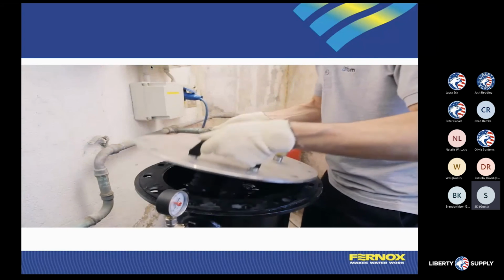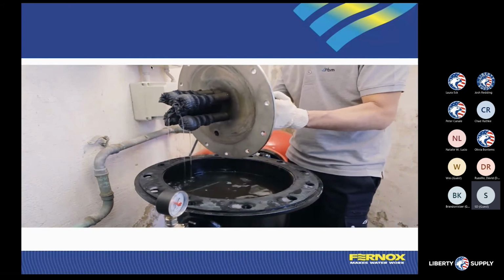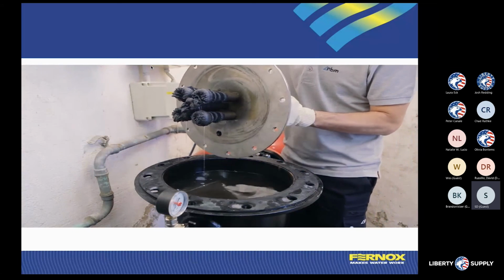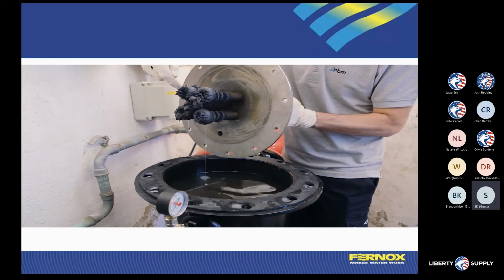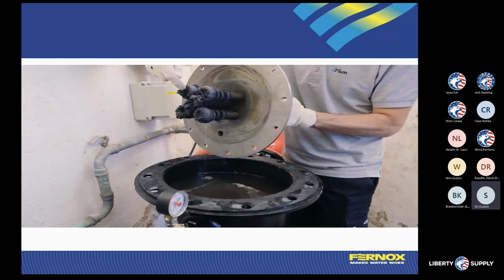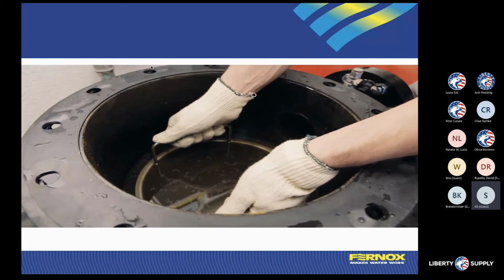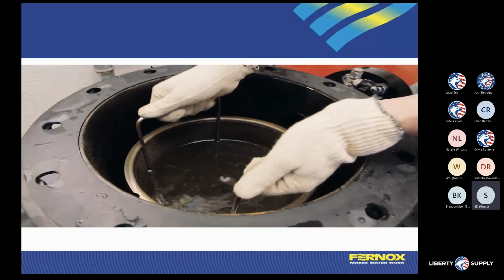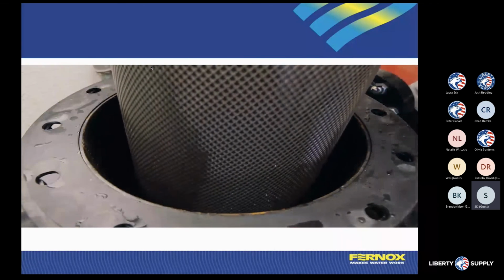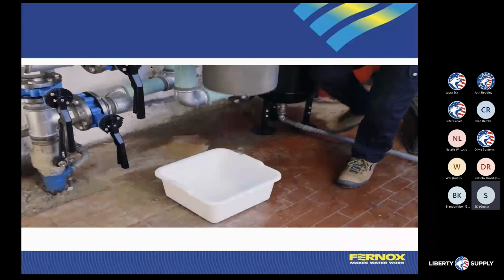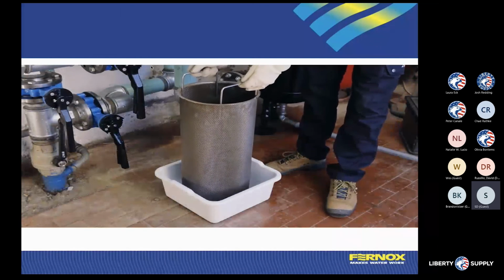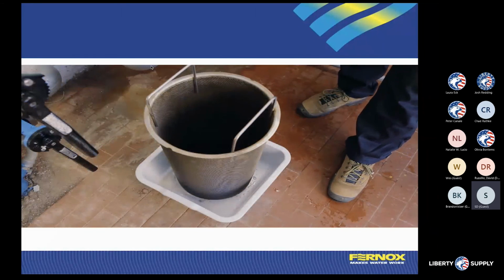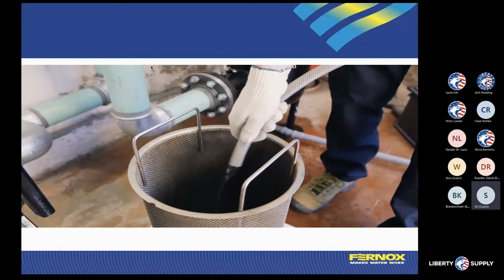So what you're seeing here is they're pulling off the screws to pull that out. And then what you're seeing there is the iron oxide that was captured at the magnet level. So from this standpoint, this is stuff that we're going to be consistently pulling out of the system and consistently cleaning. All of our Zilmet magnetic filters that we offer also have a basket strainer. So you're not only going to be able to deal with your iron oxide, but any sediment that is floating around the system, we're also going to be able to handle removing that as well.